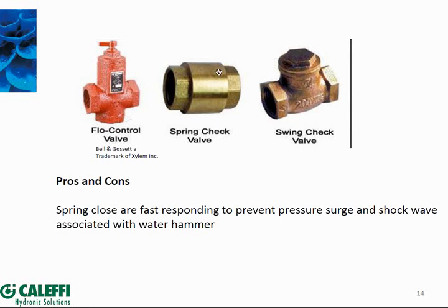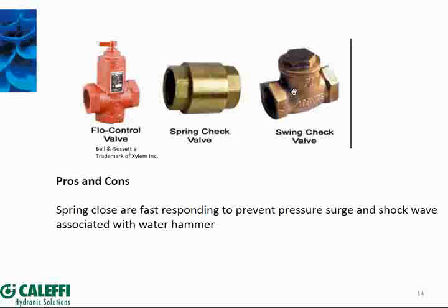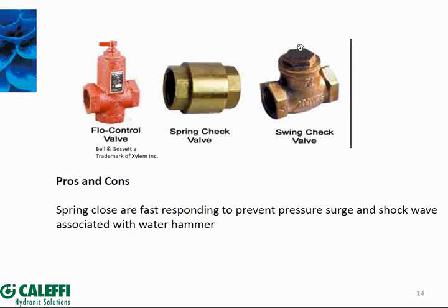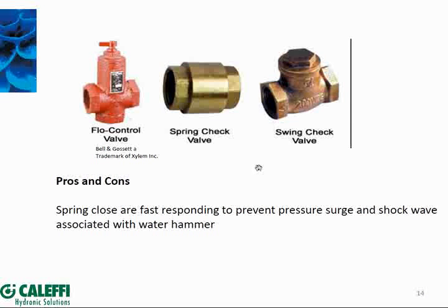Be careful with Teflon tape, pipe dope, or solder flux when installing a weighted flow check — if too much gets between the weighted plug and its seat, it will leak through. There's an important distinction: a bubble-tight seat allows absolutely no flow, while a tight seat — typically brass-to-brass or metal-to-metal — allows a little bit of flow through. In some industries that's desirable when pumping dirty water or effluents, but for most hydronic applications you want bubble-tight.